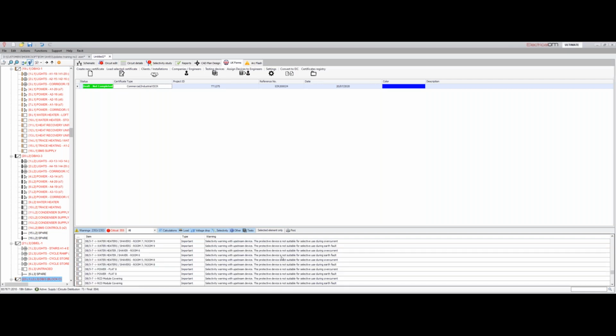Here we've got various things to do with selectivity on earth fault and also on overcurrent between devices. So all these items, generally things like voltage drop limits and those sorts of things, wouldn't be picked up by the guys doing testing on site. They may not necessarily see that information or be able to calculate it directly at site - they may not understand how to do that sometimes.